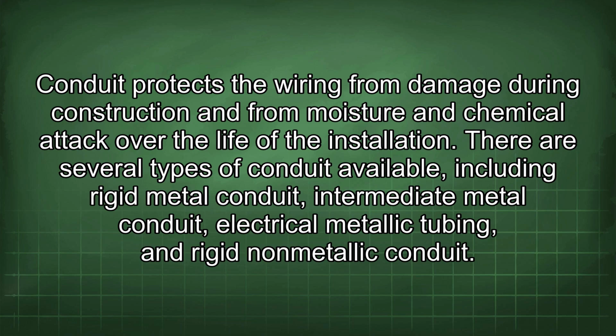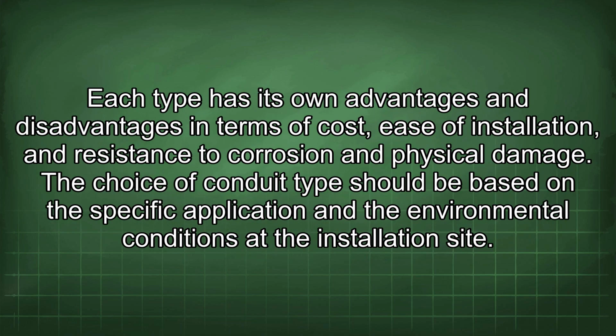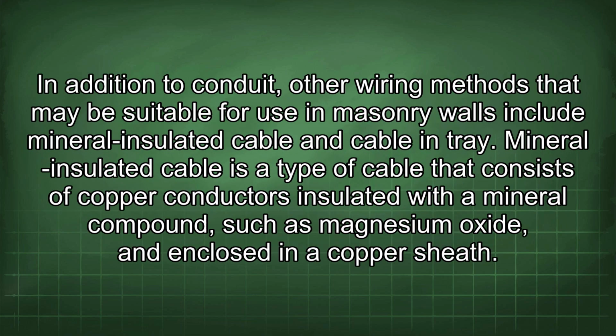There are several types of conduit available, including rigid metal conduit, intermediate metal conduit, electrical metallic tubing, and rigid non-metallic conduit. Each type has its own advantages and disadvantages in terms of cost, ease of installation, and resistance to corrosion and physical damage. The choice of conduit type should be based on the specific application and the environmental conditions at the installation site. In addition to conduit, other wiring methods that may be suitable for use in masonry walls include mineral insulated cable and cable in tray.